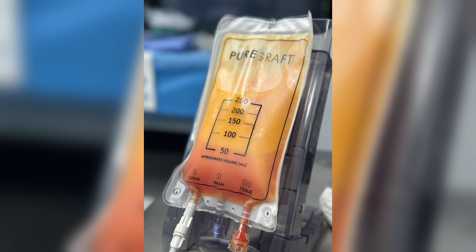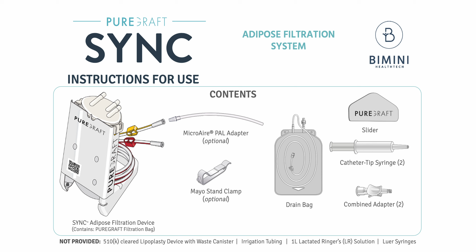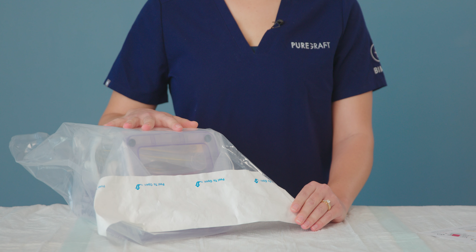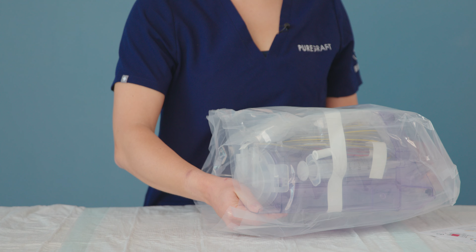Today we will go through the steps to harvest, filter, and obtain an adipose tissue graft using the Puregraft SYNC system. An electronic copy of the Puregraft SYNC instructions for use can be found on the Puregraft website. Remove the Puregraft SYNC device from its sterile packaging. Peel back the Tyvek header strip on the sterile pouch. Inside, you will find that the Puregraft SYNC is packaged inside dual-layer protective packaging. Remove the SYNC and its protective packaging from the sterile pouch and place the device on the sterile field. The protective packaging is secured with a tamper-proof sticker. Peel off or cut the sticker to remove the protective packaging.